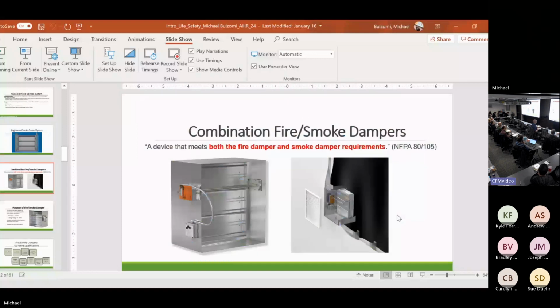We basically want to avoid doing anything to a damper once it's shipped from my factory. So the UL rule, UL states once a damper leaves the manufacturer's facility, they cannot guarantee the workmanship that's been done to the damper. Doesn't matter if I do it. Once it leaves my factory, anything, this is going to scare a lot of you, but it's okay what I'm about to say. Anything you do to a damper after it leaves the manufacturer's facility voids the UL listing. Anything. However, the industry accepts certain things.